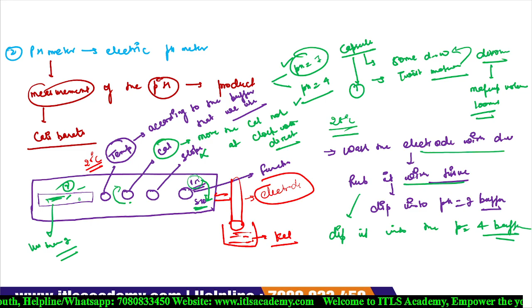Now at that time you have to dip it into the pH 4 buffer. Okay. Now after dipping it into the pH 4, we move the function knob again from the standby to the pH, and we see a value which is more than 4 on the screen. Then we move the slope button. When we move the slope button, its value decreases. Again, it is moving in a clockwise direction.